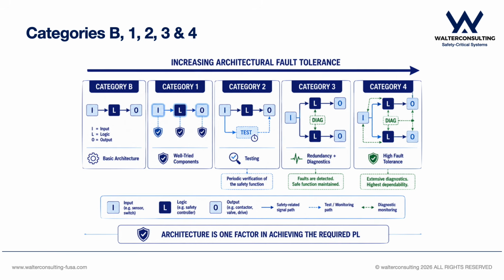One point is particularly important. A category is not the same thing as a performance level. We cannot simply say that Category 3 equals PLD, or that Category 4 automatically equals PLE. Architecture is only one part of the evaluation.